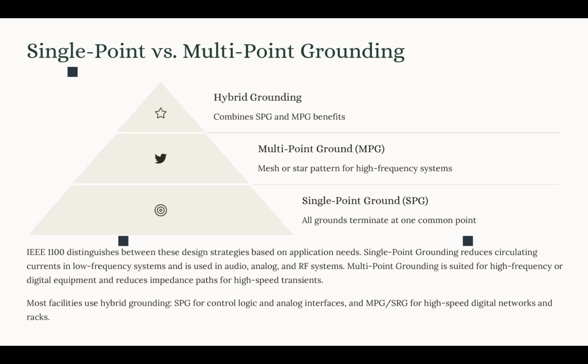Now, the next topology is multi-point ground. The multi-point ground connections are basically made at various points, so it's like a mesh kind of configuration. It's normally implemented based on that signal reference grid, that SRG that we talked about. These systems are normally used in high speed digital or broadband systems like data centers, broadcast and telecom facilities, or high frequency industrial automation systems. The pro of this system is that it has a very low high frequency impedance because we have multiple short parallel ground paths which reduce the inductive impedance. So it provides fast transient dissipation.